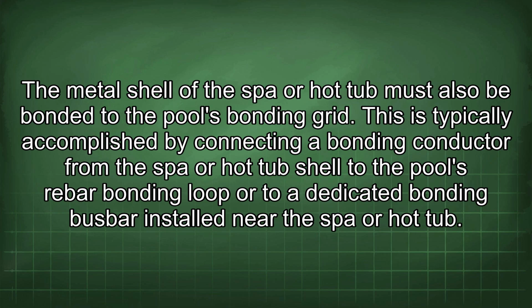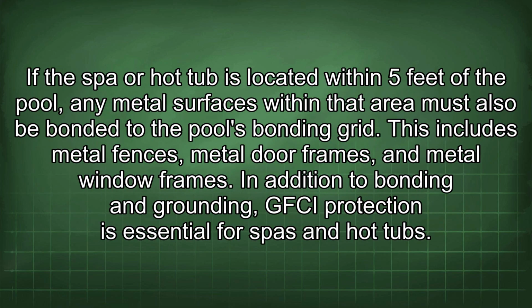This is typically accomplished by connecting a bonding conductor from the spa or hot tub shell to the pool's rebar bonding loop or a dedicated bonding busbar installed near the spa or hot tub. If the spa or hot tub is located within 5 feet of the pool, any metal surfaces within that area must also be bonded to the pool's bonding grid. This includes metal fences, metal door frames, and metal window frames.